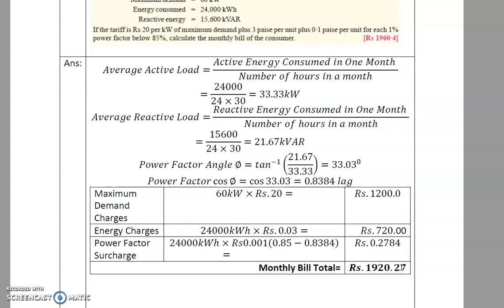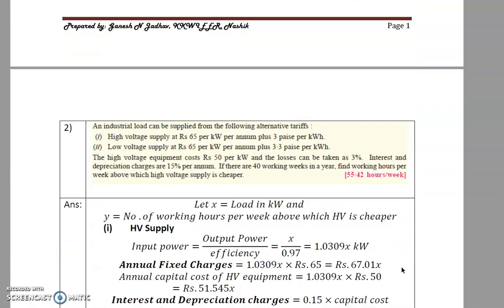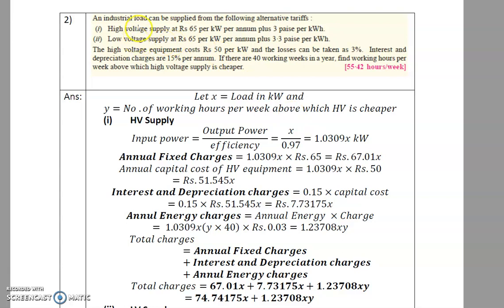Now the second problem: an industrial load can be supplied from two alternatives — HV supply and LV supply. For HV supply, the rate is rupees 65 per kW per annum plus 3 paise per kWh. For LV supply, it is rupees 65 per kW and energy rate is 3.3 paise per kWh. High voltage equipment cost is rupees 50 per kW, and losses are 3%.